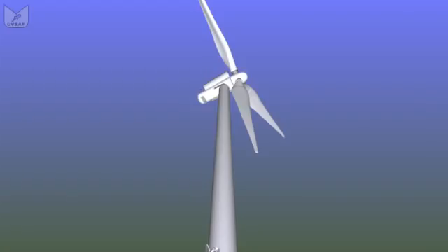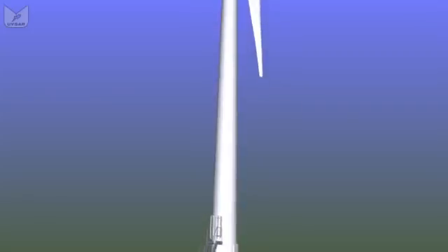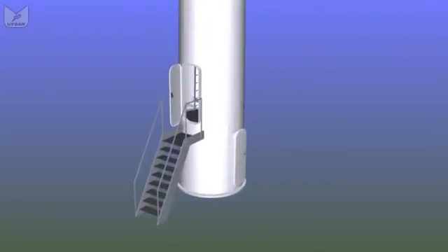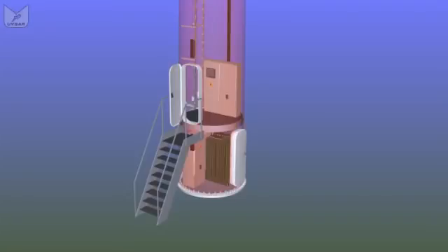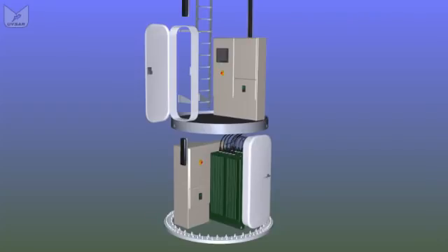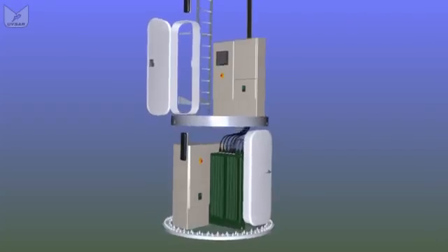Turbines of this type are typically 25 to 45 meters tall, and at the base you will often find 2 doors. The lower door takes you into a secured compartment where we have a high voltage step-up transformer. The generator at the top of the turbine is producing about 690 volts, and this transformer converts that into several thousand volts to send it more efficiently to the substation. The main entrance to the turbine is at first floor level, and there we find a control cabinet and the base of a ladder, or a series of ladders.